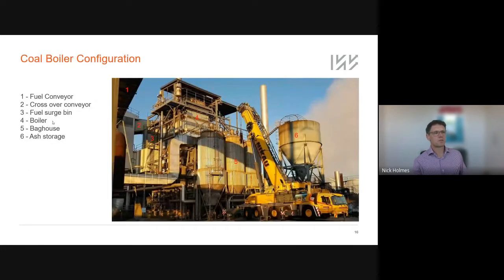So this was the existing plant, just to give you an overview of what the different components are. To the left is the fuel conveyor as it comes in, crosses over, and is then stored in a surge bin, which some people call a day bin, just a small local storage. The boiler itself is the main vertical pressure part. The three silos in the front were the old baghouse. And the silo to the right, number six, is the ash storage. So it's quite a significant size of storage in that old plant.